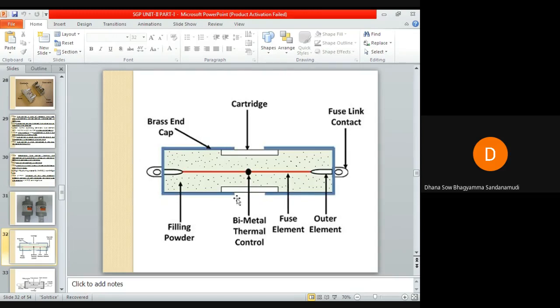So, under normal operating condition, this fuse element will be at its normal temperature. Okay, means it won't reach its melting point. Hence, this fusing element will not break and it will not get overheated because of the normal current, and hence its melting point is not reached.